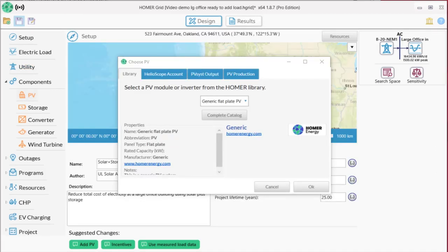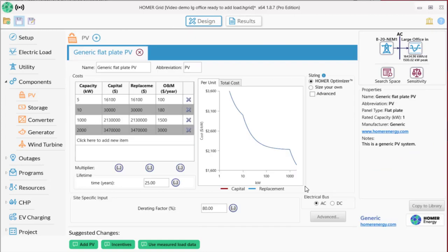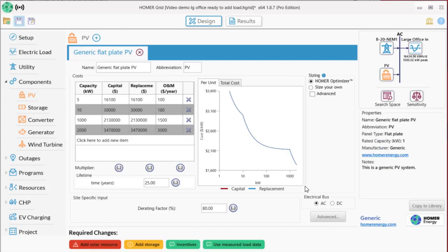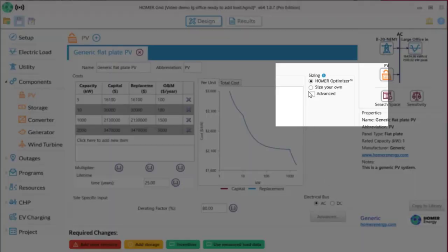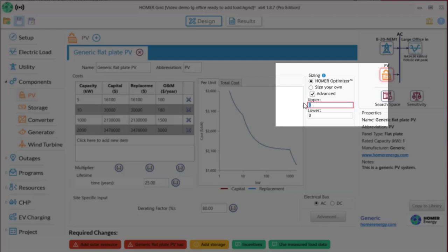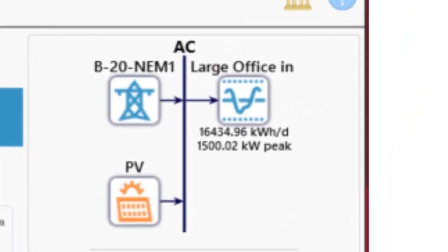Again, Homer has lots of options, including importing PV production data from Helioscope or PVSyst, importing your own data, but we just want this to be simple, so we'll use generic PV. Homer defaults to a sizing setting called the Homer Optimizer, which is a proprietary algorithm that's going to look for the best option in sizing. I recommend this when you're starting out. However, there is one important advanced setting you should use, and that is an upper limit based on your available space. This is a large office building with an adjacent parking garage, which will allow for about 2000 kW of PV, so I'll add that as an upper limit. Now our schematic shows PV on it.